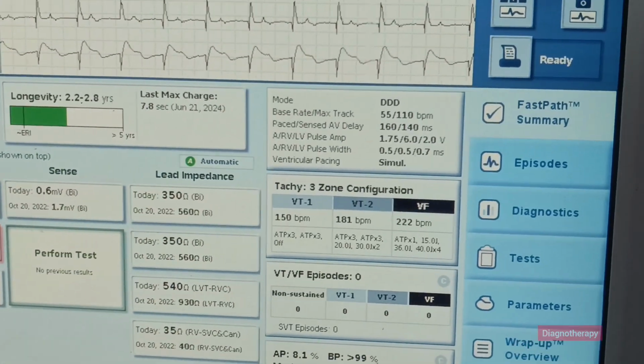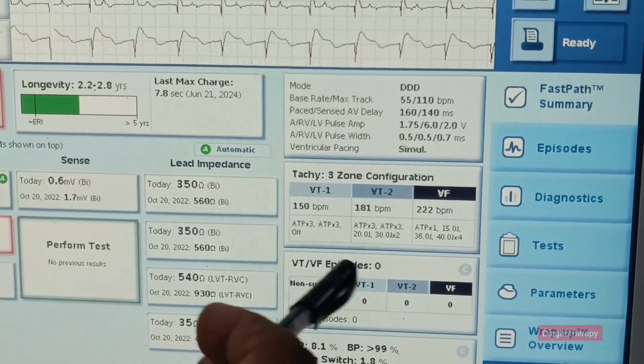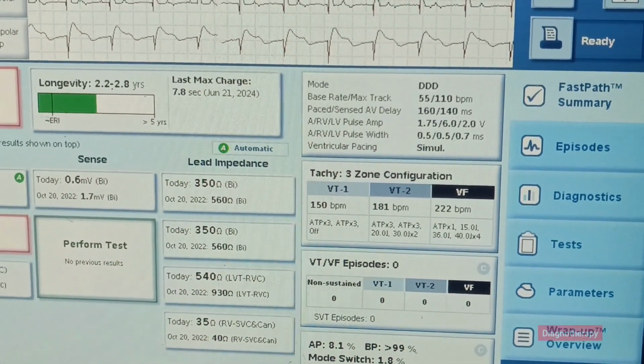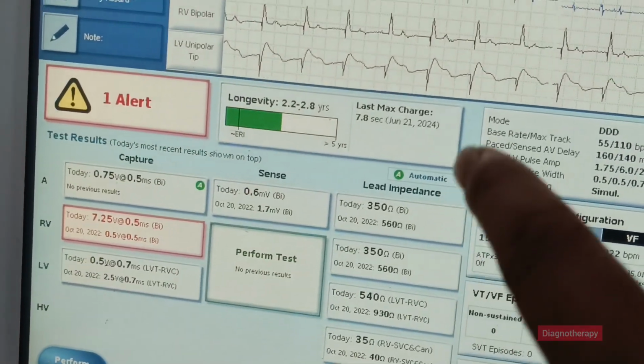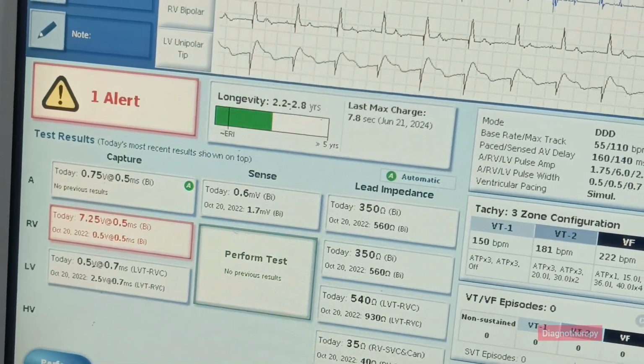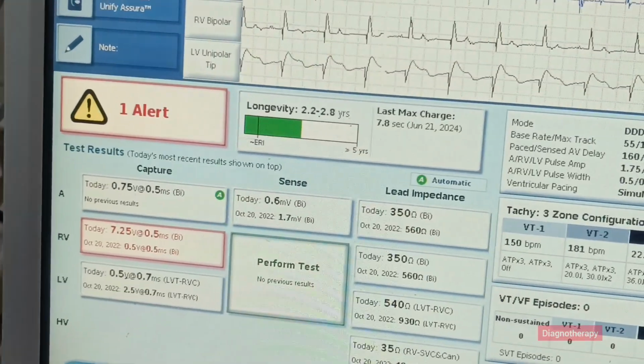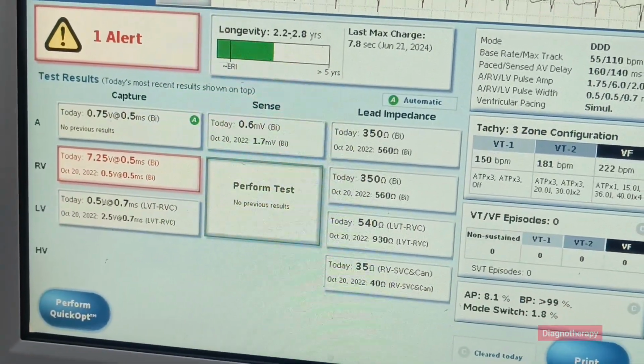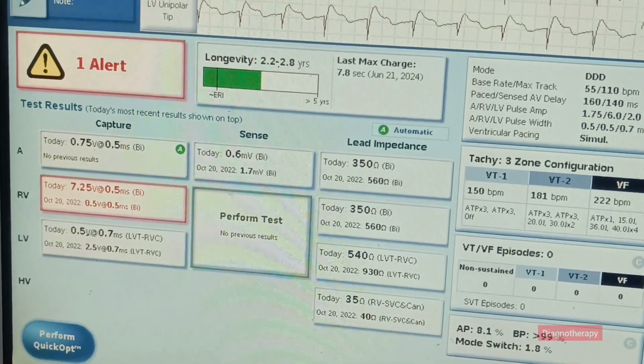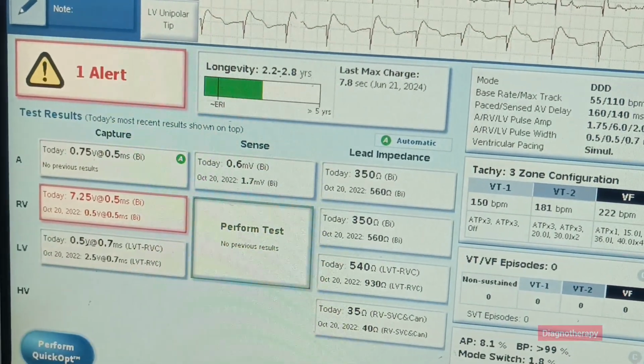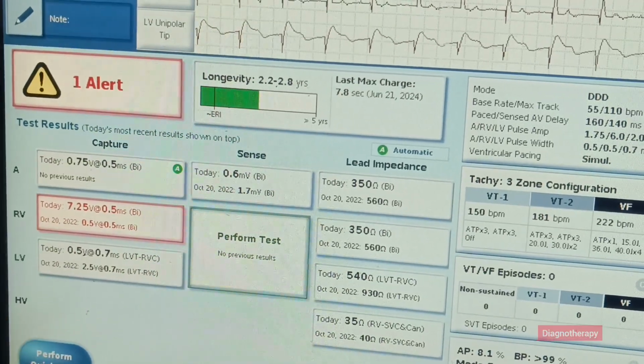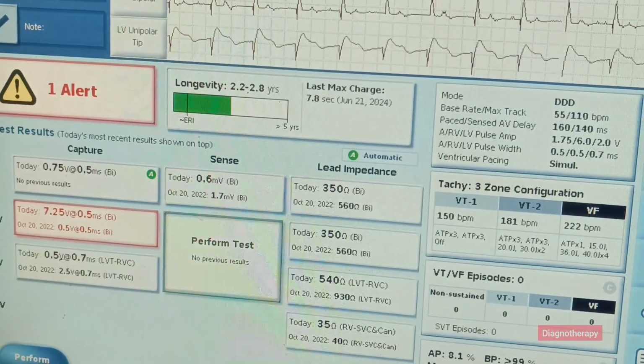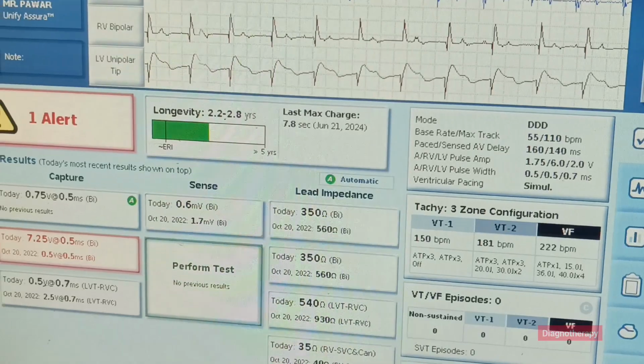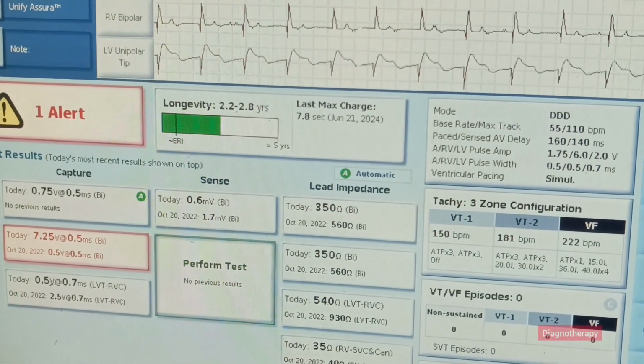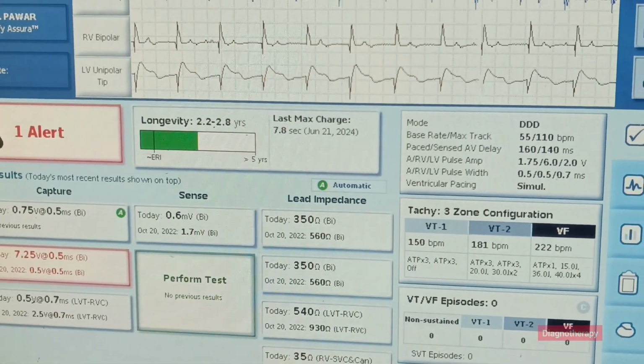If there are episodes which have come, this will log the episodes, what episodes they have been. Here in lead impedance, there are different types of resistances which tell whether the leads are functioning properly or not, if they are in proper condition or there is any breakage. So there is a range. If it goes above the range, we can tell that the leads are broken inside, or if the resistances are good, then they are in range, so the leads are functioning properly.